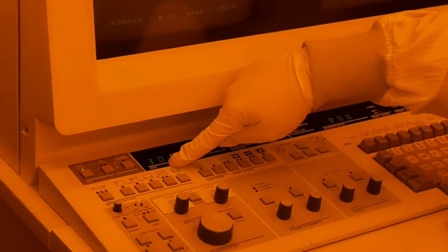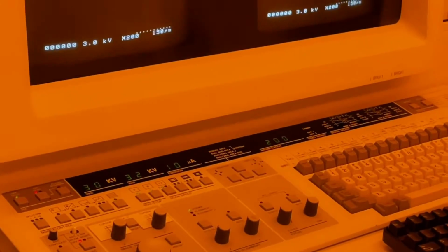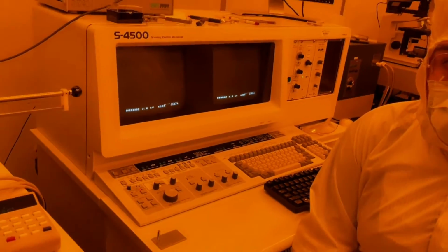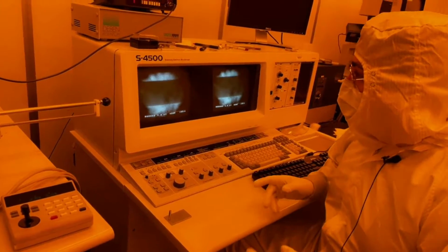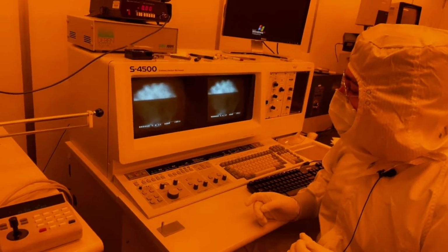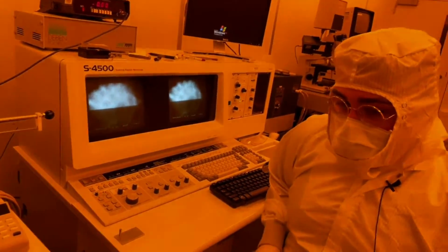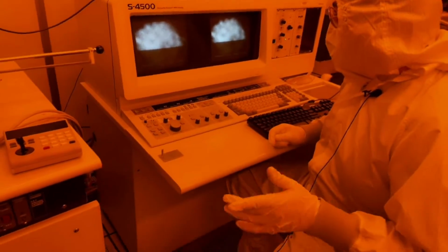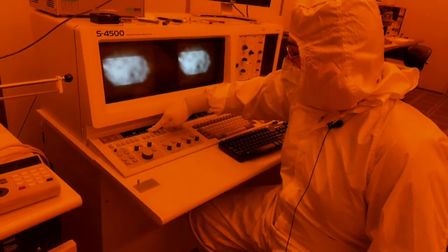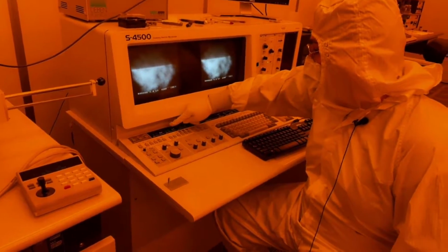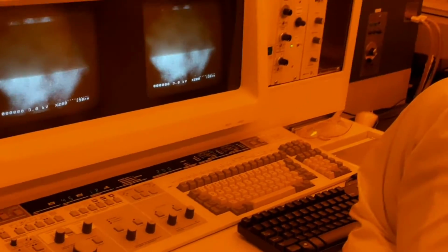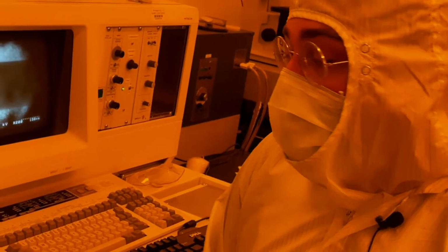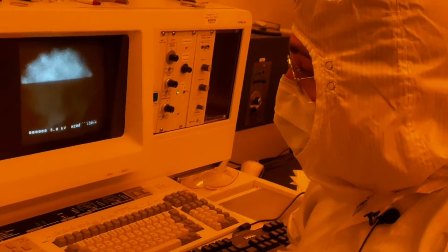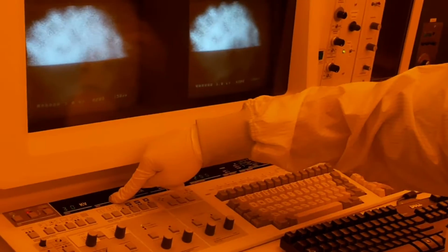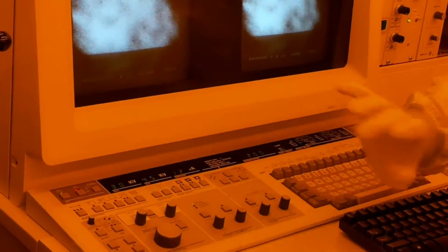We're using an acceleration voltage of 3 kilovolts. There is literature published on the best acceleration voltage to get good images, as a relation to what kind of charging and what effect it might have on your sample. We also have our extraction voltage here. You can see it's at 4.5. Ideally, we should be able to get it to 4.3 if we're regularly flashing it. So since it's already at 4.5 before we start, I'm going to flash it one more time.